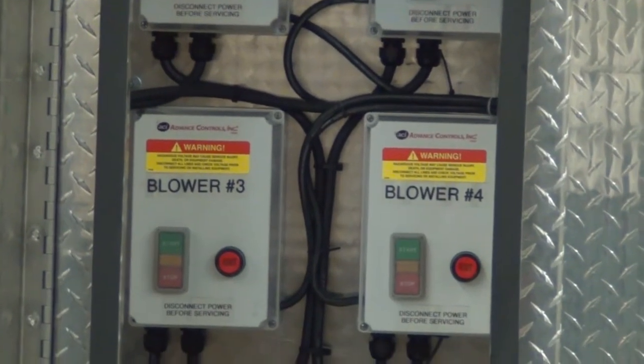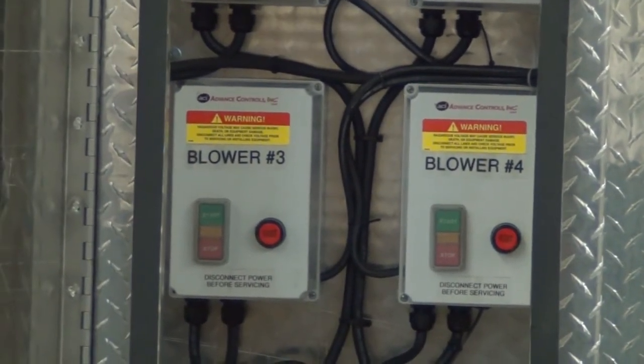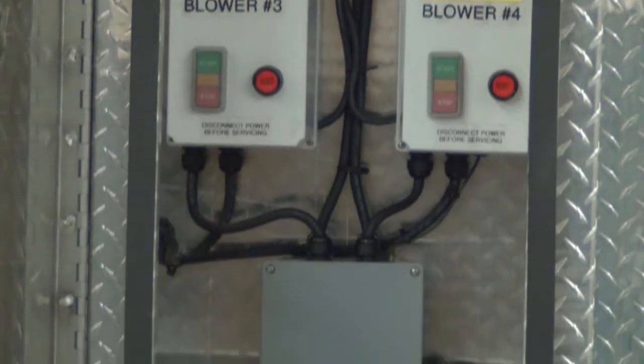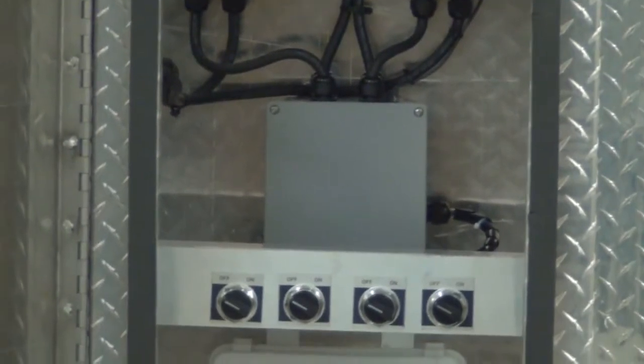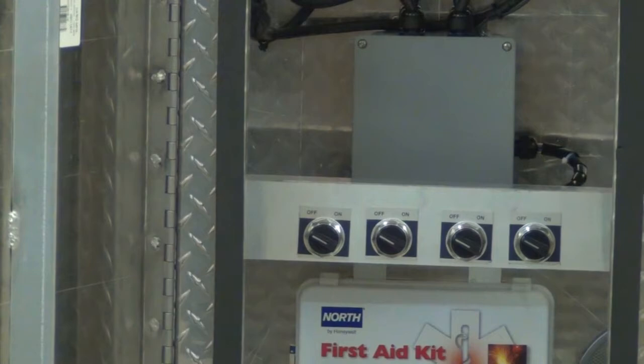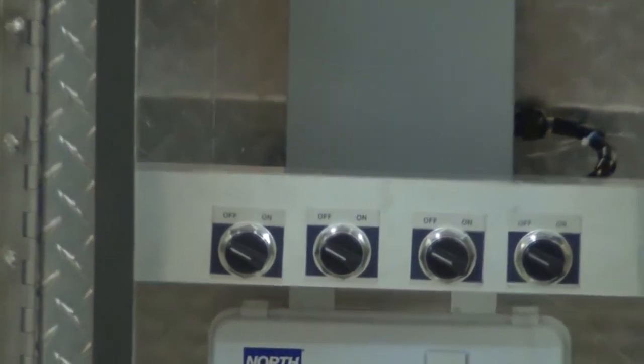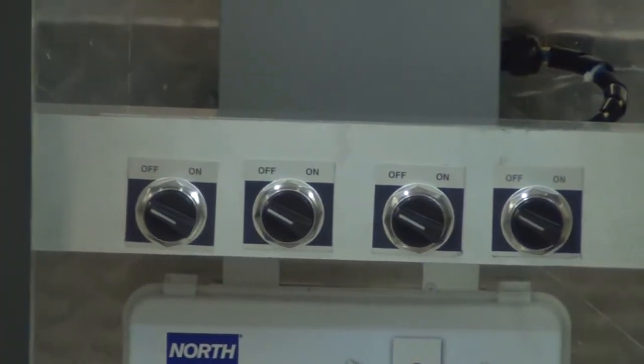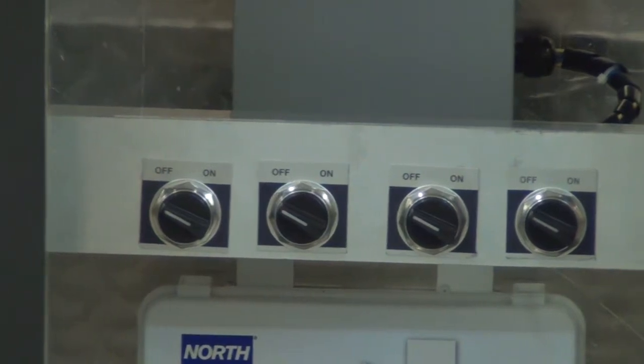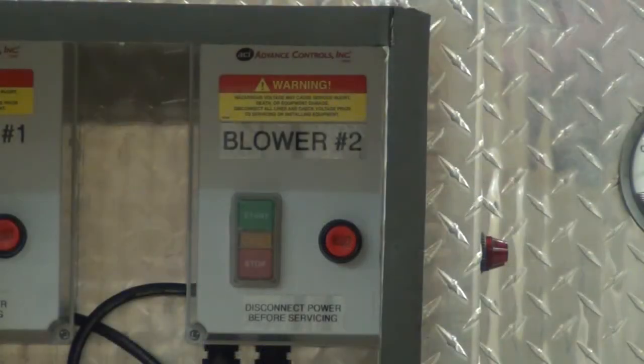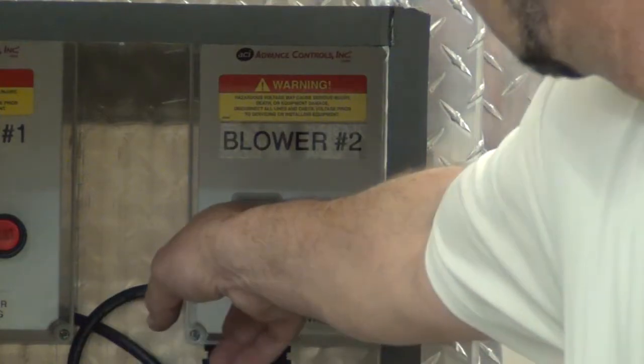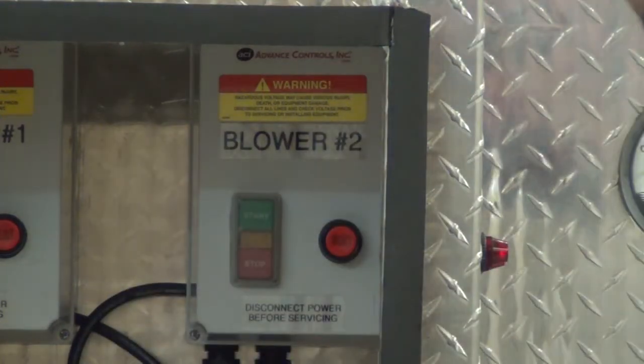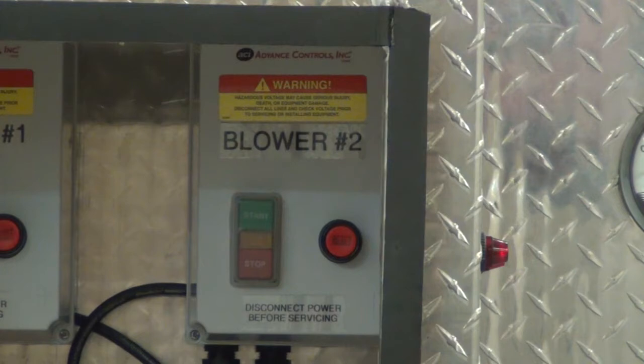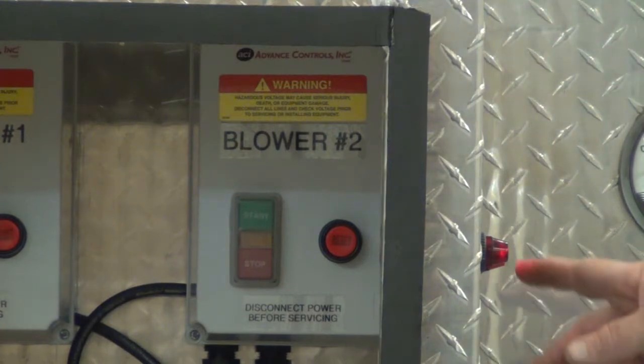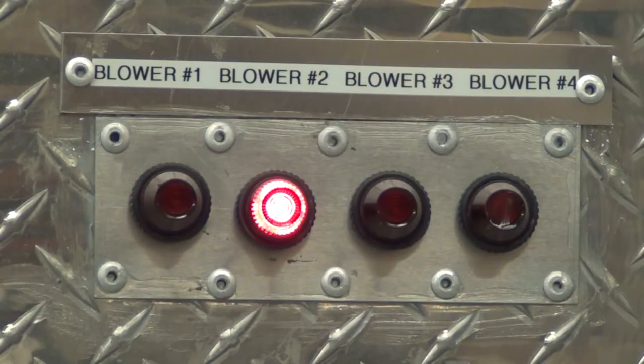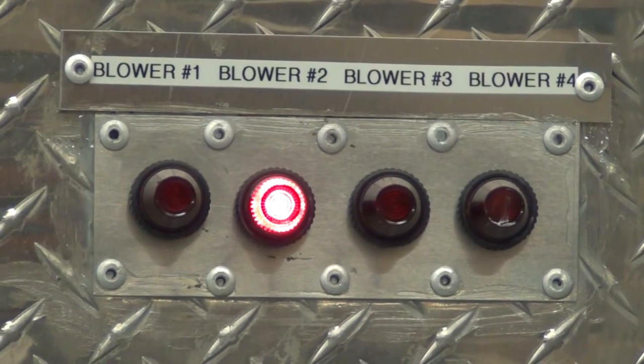These motor starters are connected to a variable frequency inverter, which allows for a slow start, low amp draw start. Once the starters are engaged, the individual blowers are energized by these on-off switches for the individual blowers. We'll go ahead and push the start contact for blower number 2. This will also energize a light on the side of the panel to indicate power on to that circuit. This light indicates power on to blower number 2.